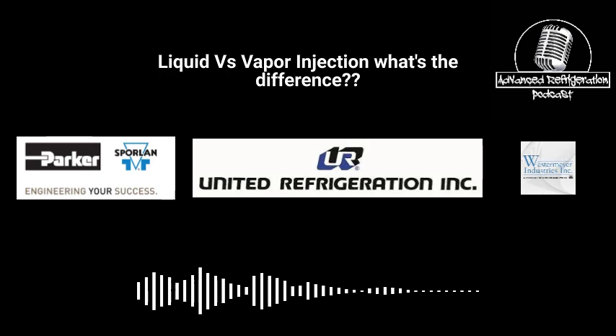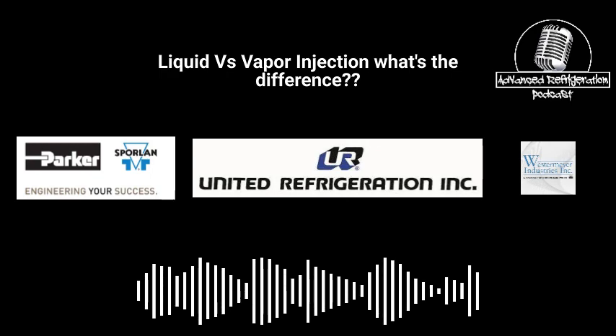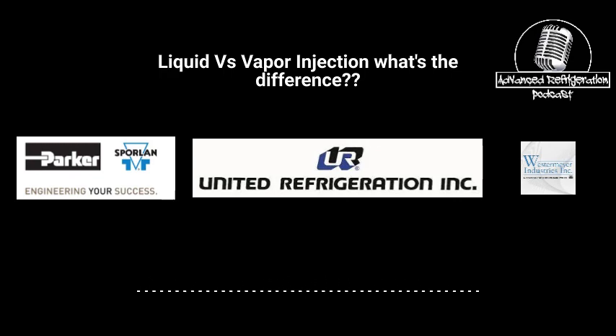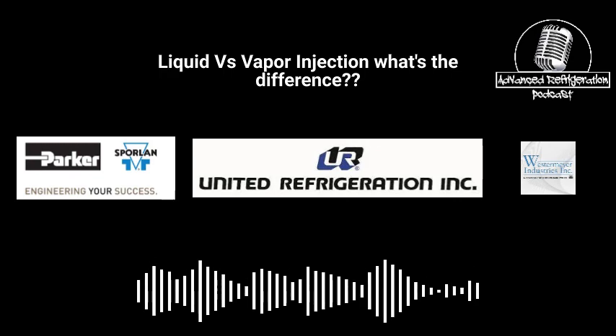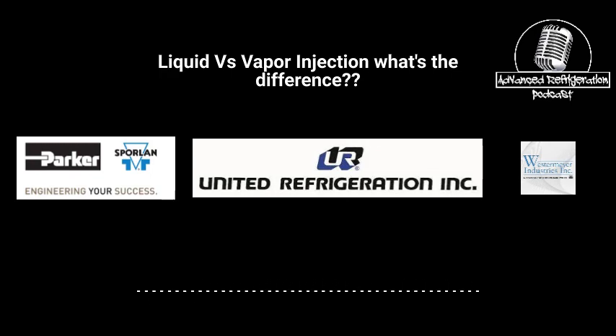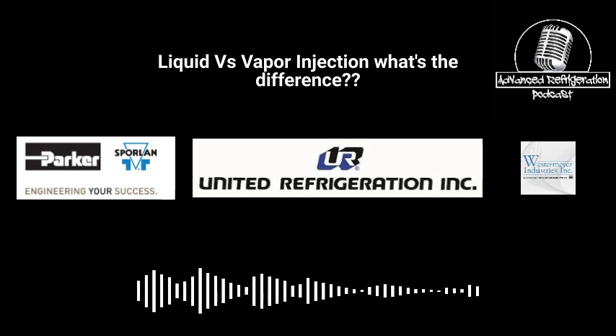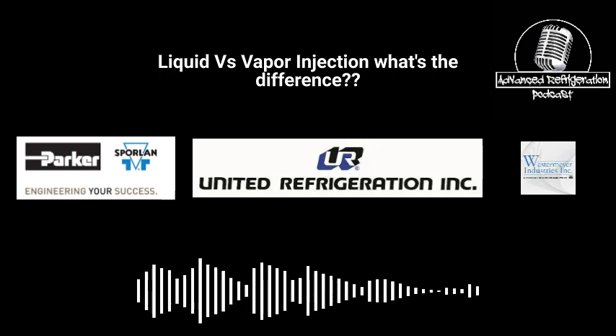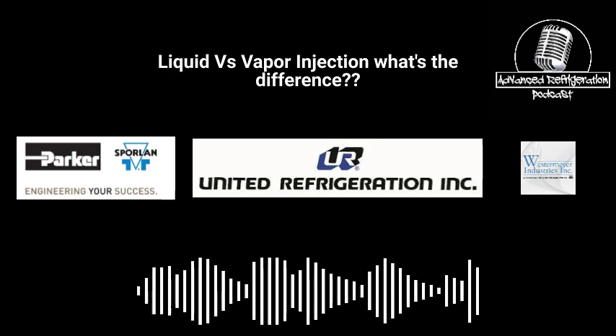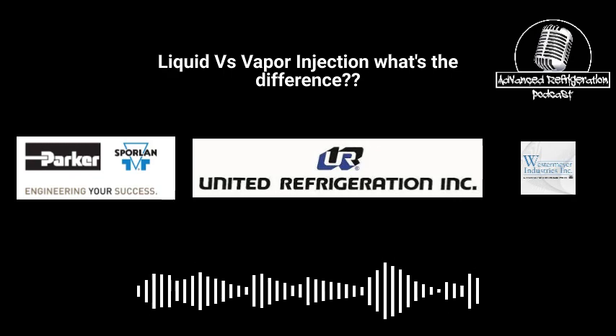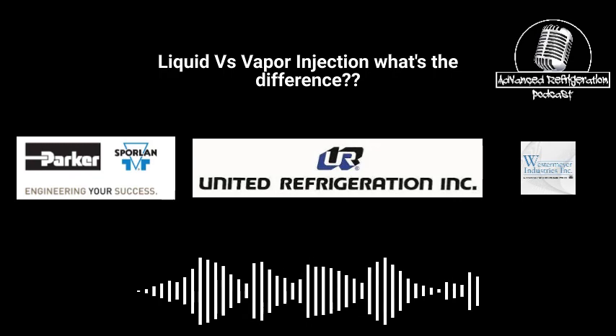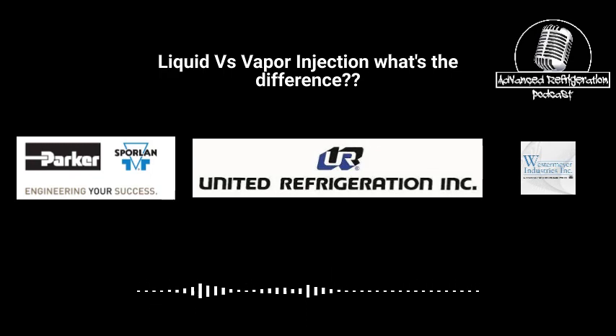Also, with those valves, I don't think you can replace the orifice on the inside of those. You can. Okay, so on the Y1037, you can replace the orifice. My bad. And you can also replace the power head, which is really awesome, because if whoever installed it didn't make sure the valve bulb had no vibration or didn't rub up against something, and that valve breaks, theoretically you'd have to yank that one out and weld in a new one. Well, thank God it's exactly like a regular conventional power head, where you can undo it and put on a new one. The orifice, all you need is a 3/8 nut or a 5/16 nut driver, and you can just unscrew it. That valve is super simple. It is literally a piston or a needle, a seat, and the power head.